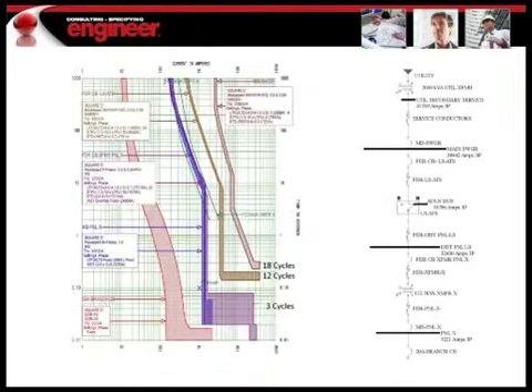And what we wind up with is we have a transfer switch that has to be able to withstand at least 38,500 amps of fault current, and that it has to be able to interrupt that current for at least 12 cycles. So this is a rating that probably is beyond that which has been tested for a 400 amp switch. Some manufacturers currently produce switches that are rated at 30 cycles. So in this particular case, we would likely have to specify that our transfer switch was able to tolerate 38,500 amps for at least 30 cycles. So this is an example of the impact that selective coordination has on the specification of automatic transfer switches.